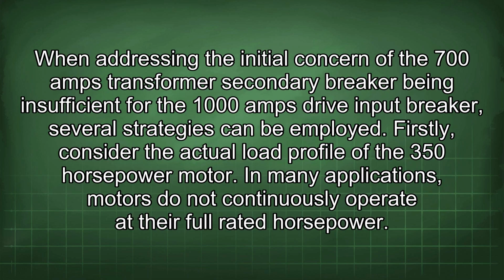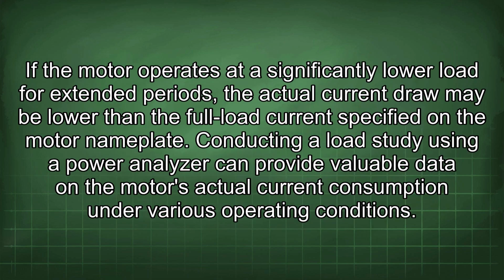requirements. When addressing the initial concern of the 700 amps transformer secondary breaker being insufficient for the 1000 amps drive input breaker, several strategies can be employed. Firstly, consider the actual load profile of the 350 horsepower motor. In many applications, motors do not continuously operate at their full rated horsepower. If the motor operates at a significantly lower load for extended periods, the actual current draw may be lower than the full load current specified on the motor nameplate.